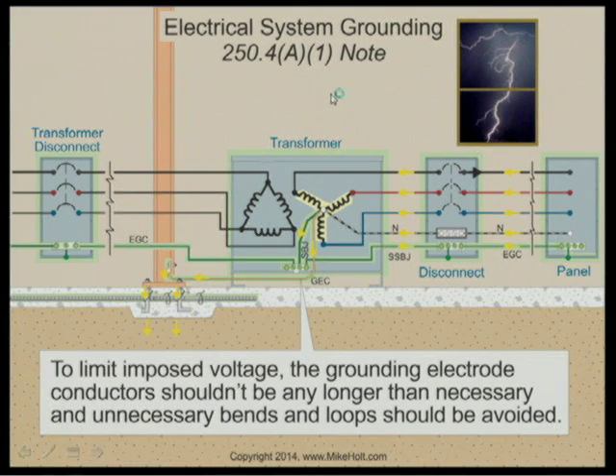On a grounded system, there's an informational note in 250.4(A)(1), and it says this: the grounding electrode conductor should be no longer than necessary, and you should avoid unnecessary bends and loops. And the reason being is this conductor right here is not carrying fault current. This conductor right here is carrying high frequency transient energy to the earth. The size of the conductor really is unimportant. What really matters is the length of the conductor, because high frequency current travels on the outside of the conductor. So you really want your grounding electrode conductor to be as short as possible.